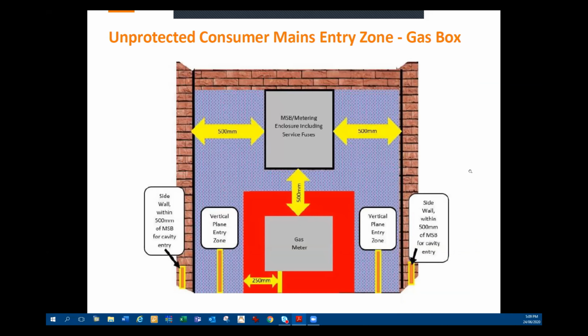Now, if you could possibly confirm for me and everyone else, a lot of people are requiring a lot more space in their switchboards now when they're installing other sources of supply, such as generators, solar, batteries. In doing that, they may require a larger switchboard. If someone is to replace a switchboard that is one brick away from the gas meter, are they now required to install their larger switchboard 500 mil away from the meter, or can they utilise the distance that was already there, provided they don't go any closer?